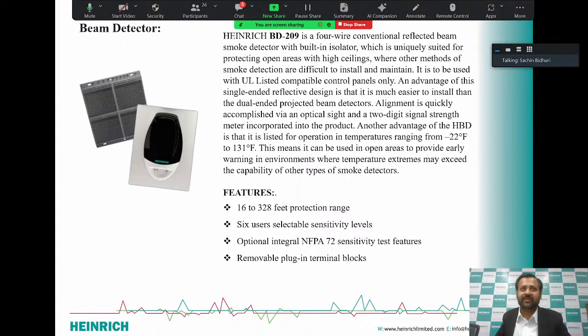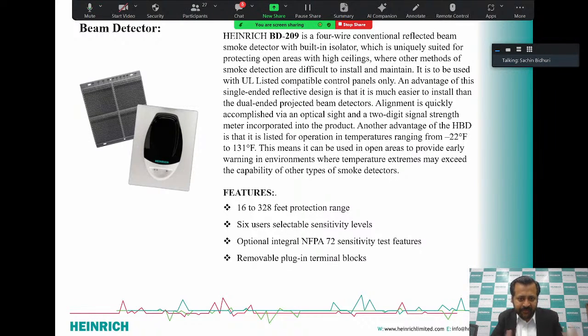In many plants there is a ceiling height of up to 15 meters or maybe more than that. In that case, we install our beam detector. It is a type of detector which has a transmitter and a receiver. The transmitter is installed on, let's suppose, the left side of the room, and the receiver is installed on the right side of the room. After installing them, there is a beam that comes from the transmitter to the receiver, and in case any smoke goes through that ray, it gives a signal to the fire alarm panel, and the hooter starts informing about the fire.